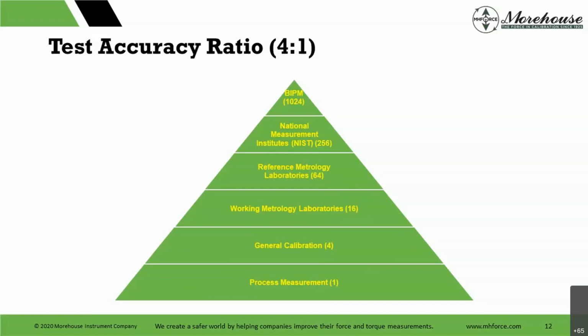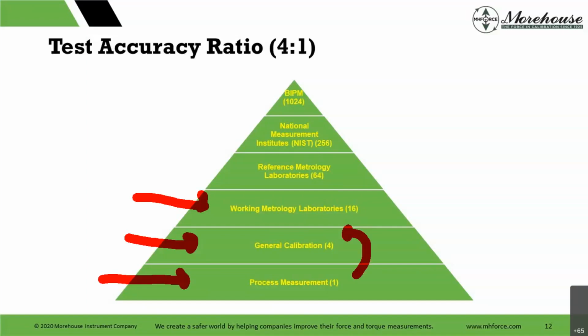And it's not problematic when it's confined, meaning if I had an agreement with somebody else on this call today that said, hey, we're going to calibrate and it's going to be 4 times better than your expected performance characteristic or your accuracy, that could still work, right? But this picture right here shows that it doesn't work when we're talking about measurement traceability, which we talked about last week, which is each measurement contributing to the measurement uncertainty. So every stage here with this pen, each one of these has to contribute to the measurement uncertainty. If we look at a T.U.R. and build it out, we start here with process measurement or working standards, and then we're going 4-to-1 up. That's probably achievable. Another 4-to-1 up, probably achievable. And now we're getting at a 64-to-1, a 256-to-1, a 1024-to-1. That just does not happen.